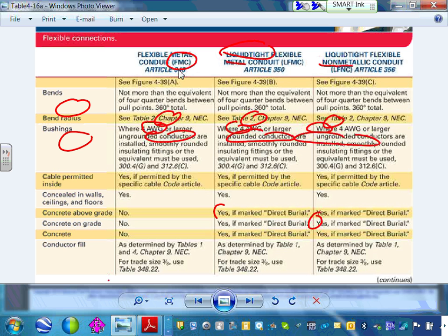Remember, anything non-metallic - yes, yes. When you bury things, direct burial, non-metallic for burial, yes, if marked for direct burial. Concrete - above grade, or on grade level, in concrete, you can use the non-metallic. I always tell people, if you're putting things in concrete, buried in concrete, and you don't know which conduit to use, always think non-metallic. You don't want to bury metallic conduits for the most part. You're always right.